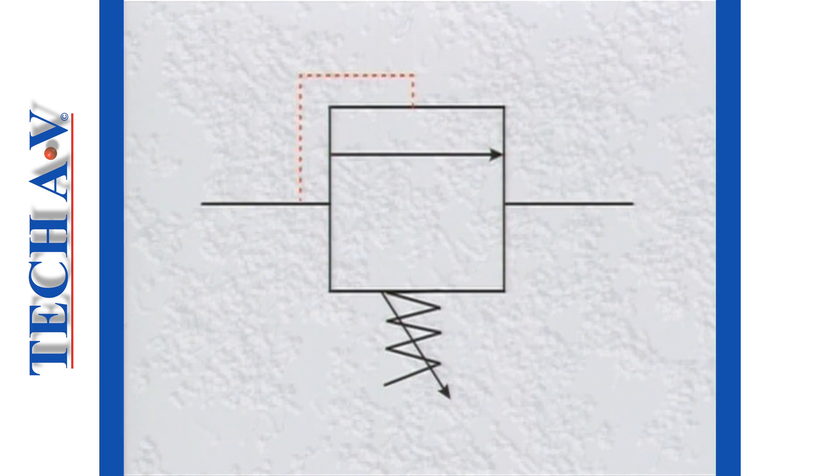The dashed line indicates that the valve is operated by pressure from the working line. The spring symbol tells us that the valve is held closed with spring tension. The arrow drawn through the spring indicates that the spring tension is adjustable.